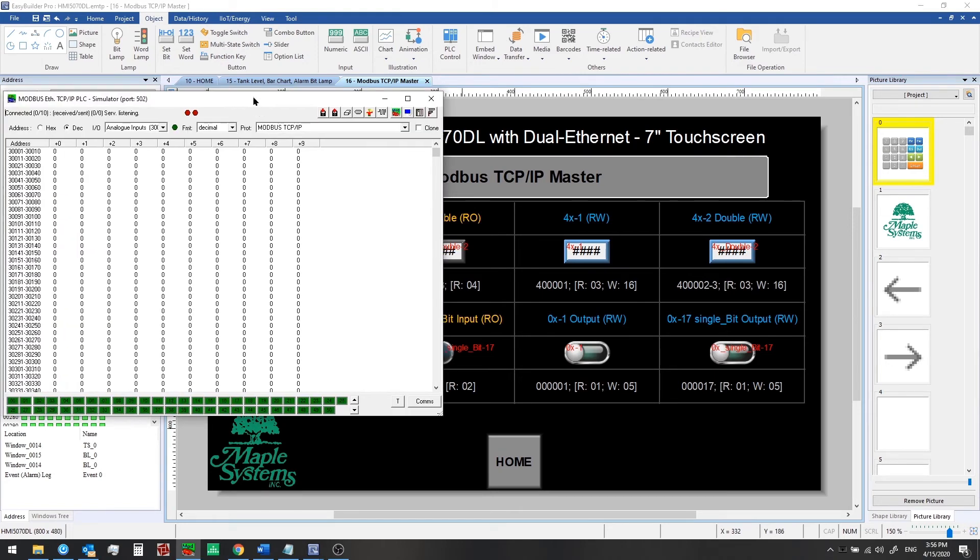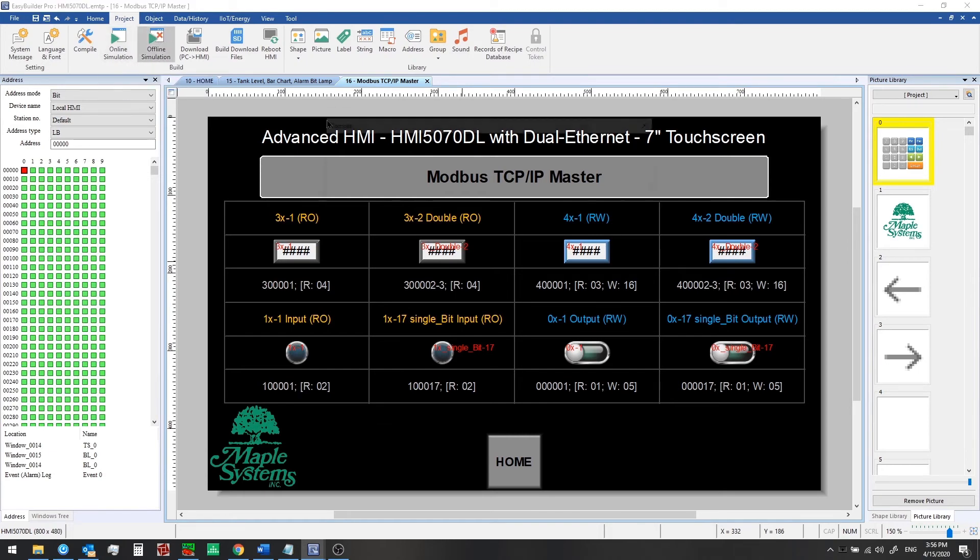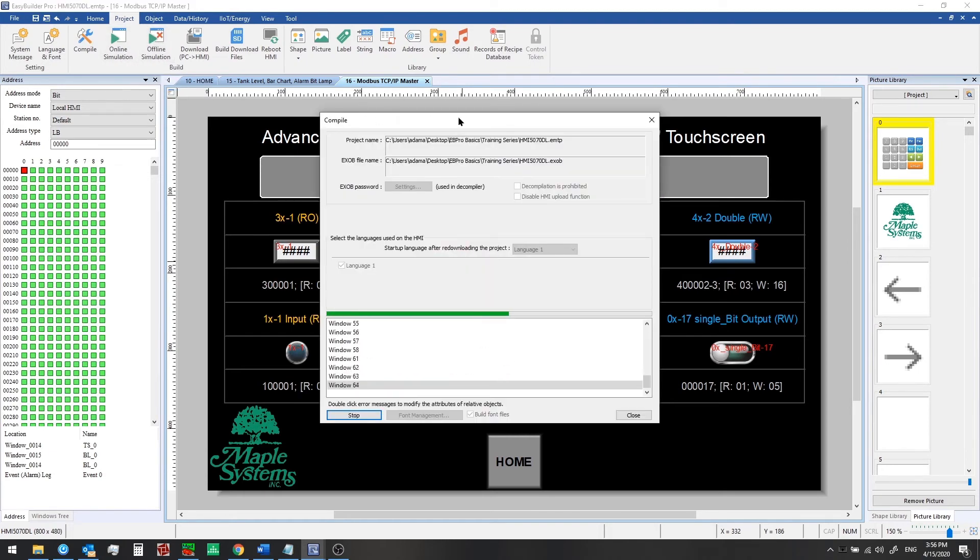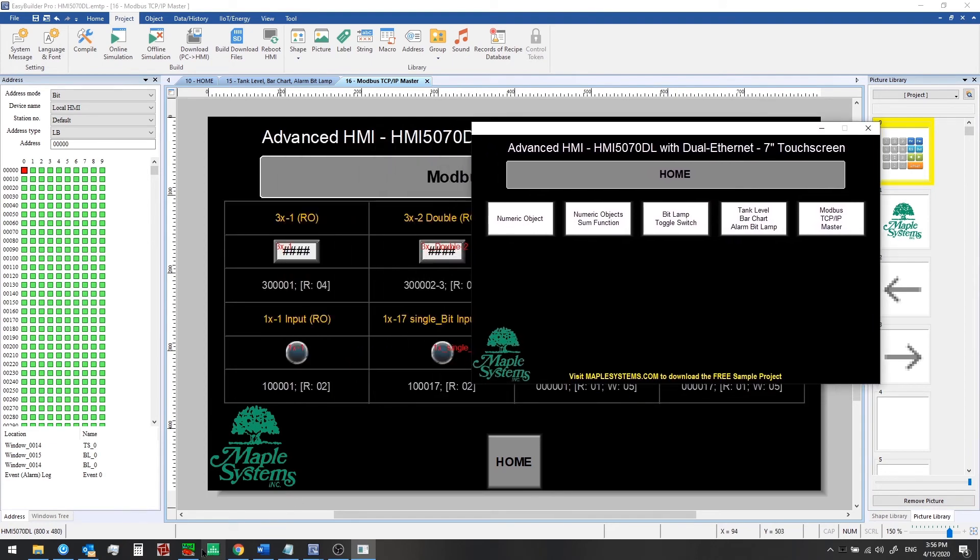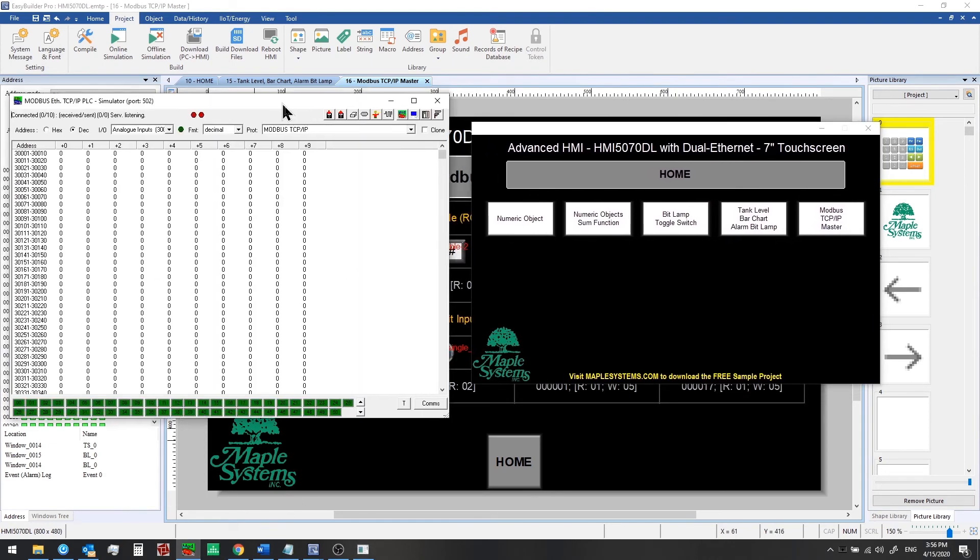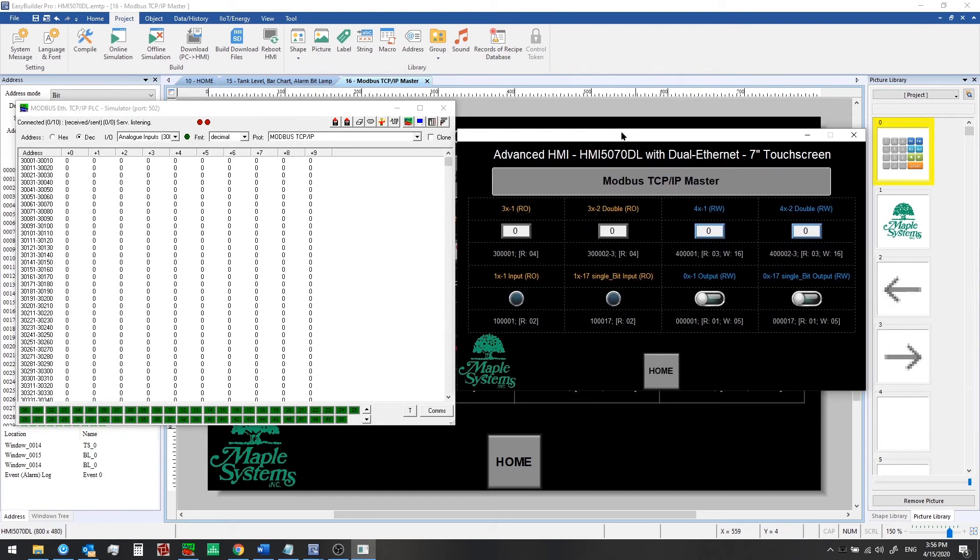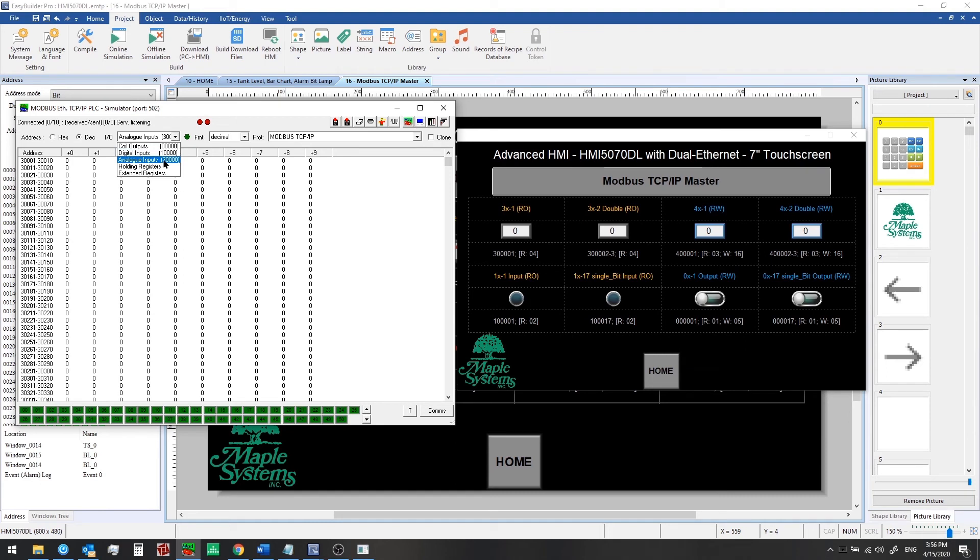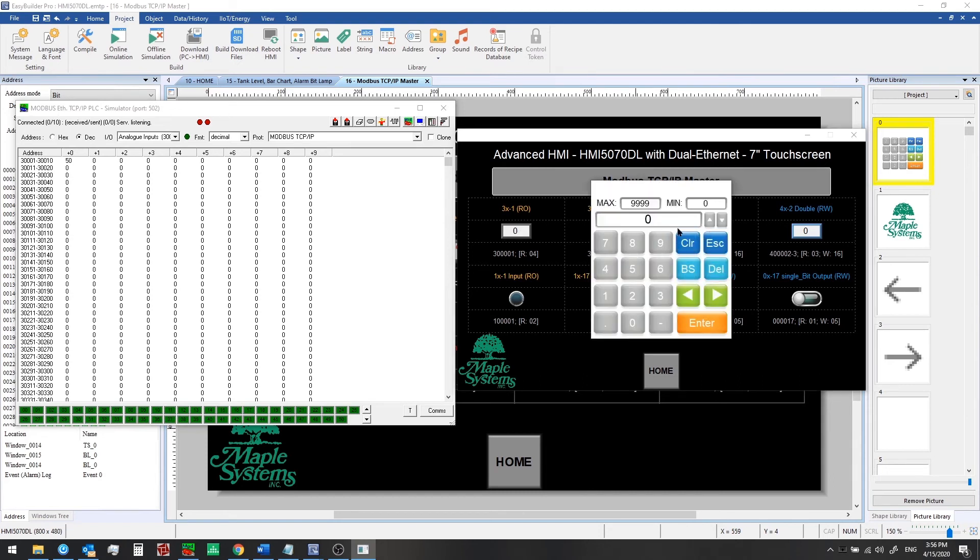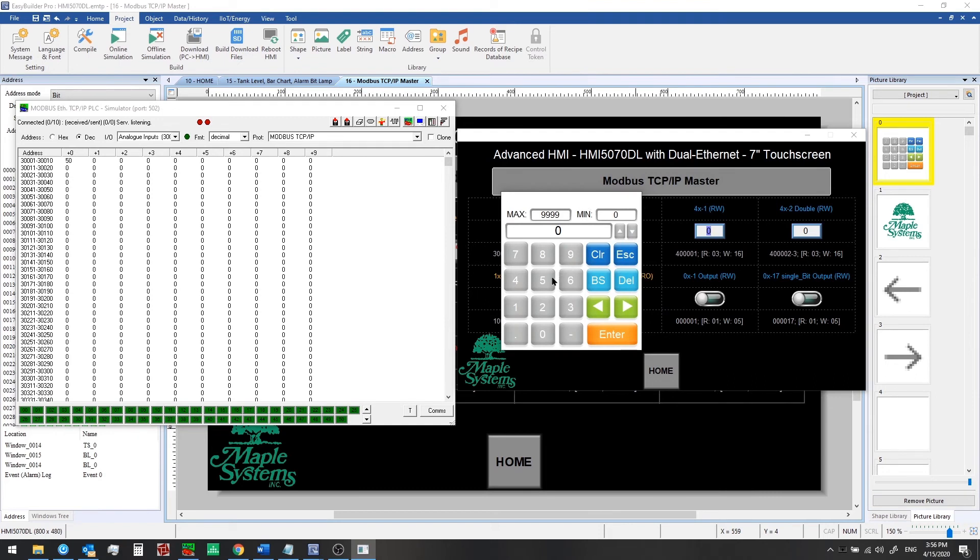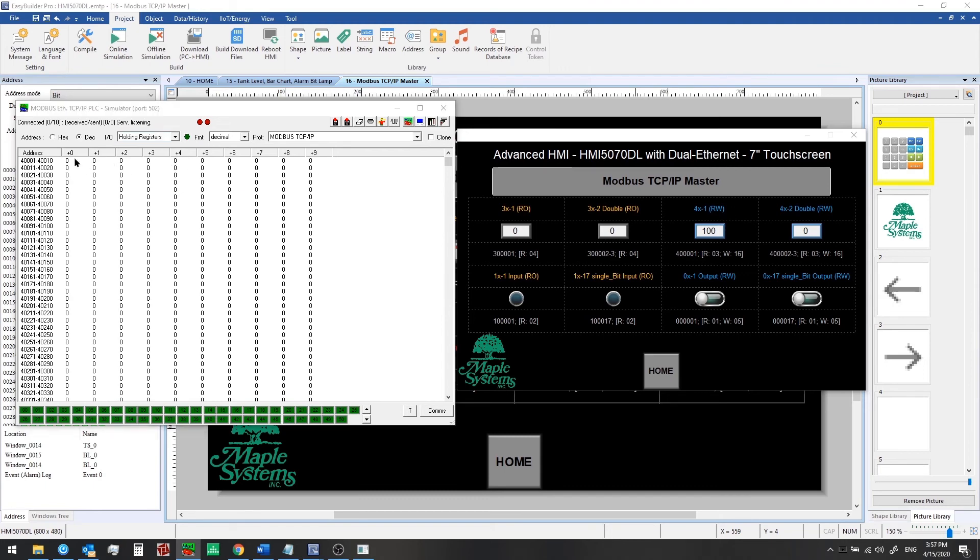We have our Modbus simulator program open now. We're going to run the offline simulation first. After that, we'll run the online simulation and you can note the difference. Remember, offline simulation will not try to communicate with your PLC, and online simulation will. We'll go to the new Modbus window that we've set up. Let's go first to the analog inputs, so the 300,000 range. We're going to change the value - we're going to force the value to 50 here. Notice in our offline simulation, we do not see that value show up. Similarly, if we enter a value into the holding register in 4x1 and we switch over to the holding registers here, we do not see that value show up.